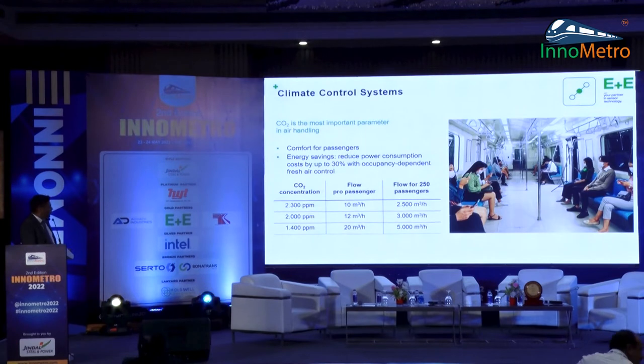To maintain 1400 ppm CO2 concentration, which is very bad air, people normally want to have 800 to 900 ppm as the air. You still have to run your AC system at 5000 meter cube per hour, which is almost half the capacity of the RMPU. So you always have to maintain the balance between whether I need to give good air or I need to run the AC at the highest capacity. That's the kind of challenge you have, and with CO2 monitoring you can obviously increase your efficiency and decrease the consumption of electricity and energy.